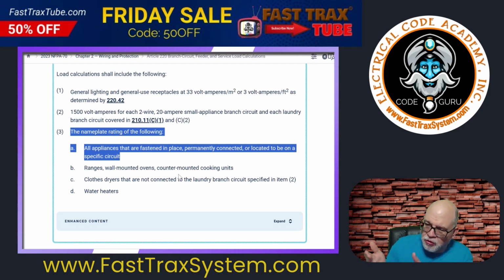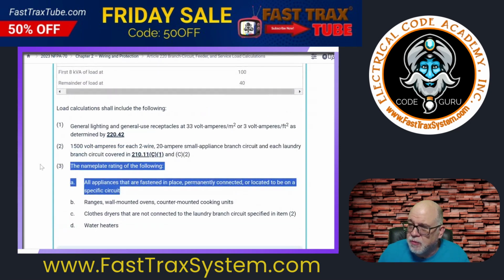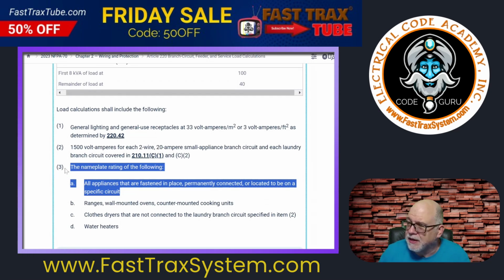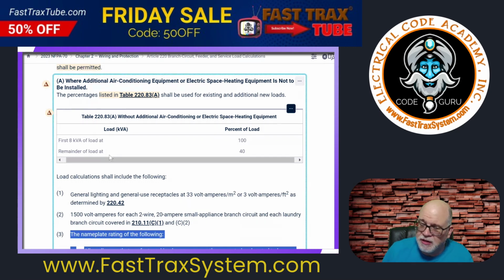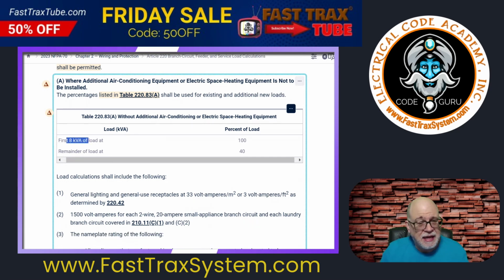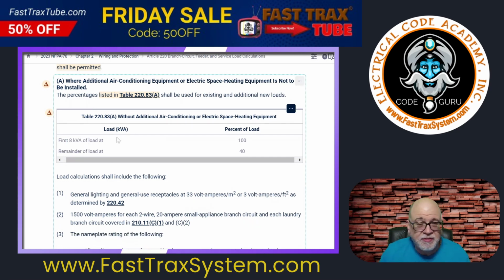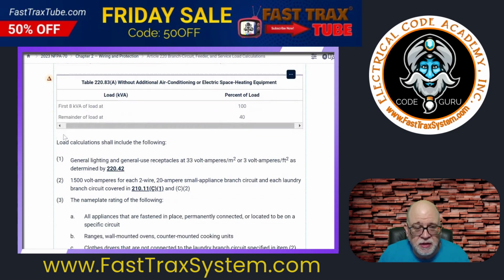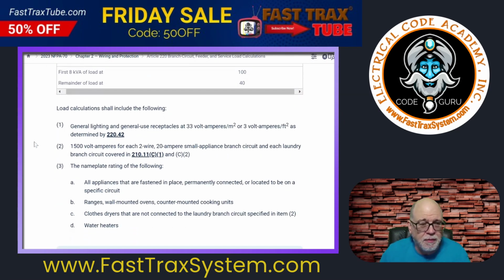Now, since you have to gather all of the information anyway, then you might find that you're better off doing the optional method anyway. Okay, and that means the first 10,000 is at 100%, and then the remainder at 40%. But this method might be a little smaller because only the first 8,000 is at 100%. Okay, so if it's existing, you're permitted to do this. Okay, so you could go back and use the optional method or even the standard method, but you're permitted to do this. This might yield something that's going to work out better for you.